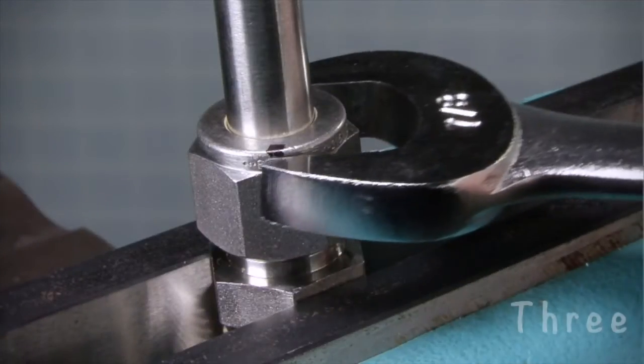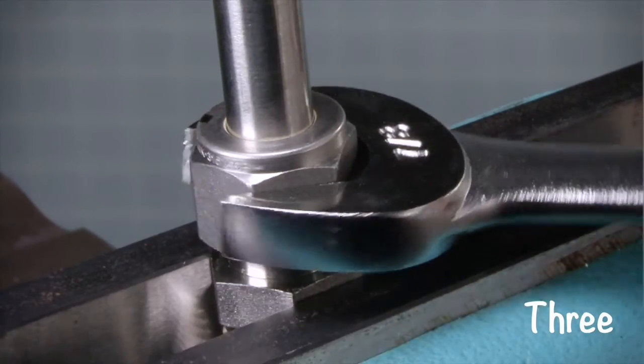Step 3. While holding the fitting body steady, tighten the nut one and one quarter turns to the nine o'clock position and the job is done.